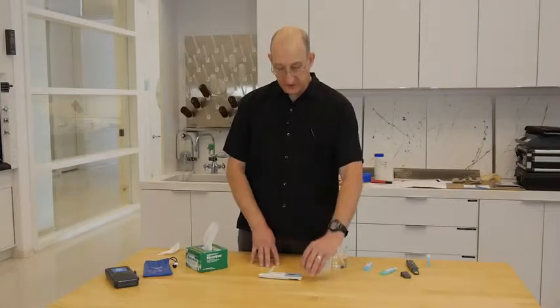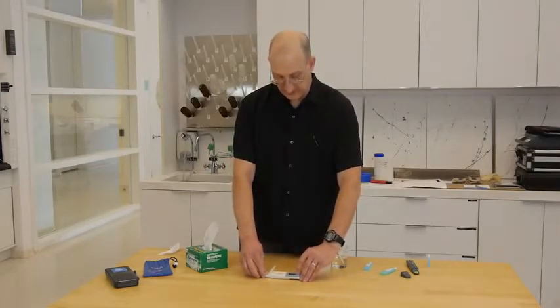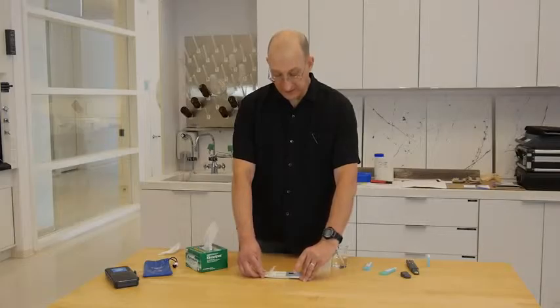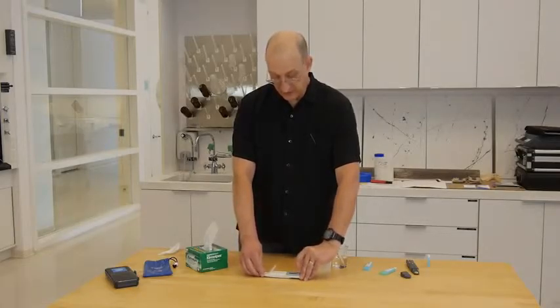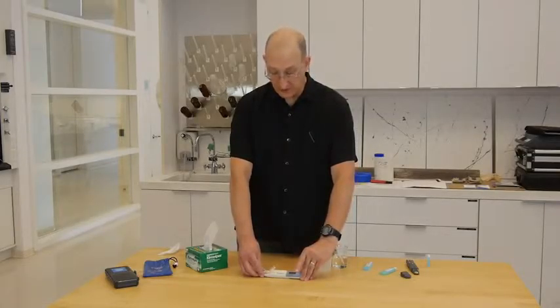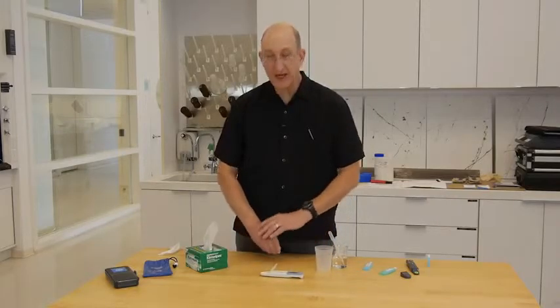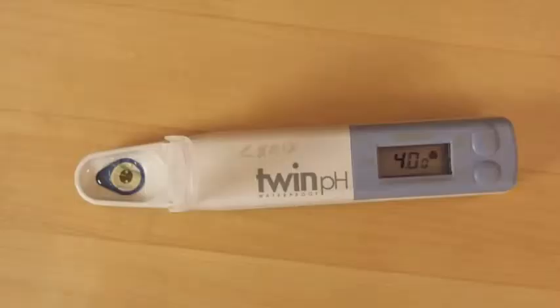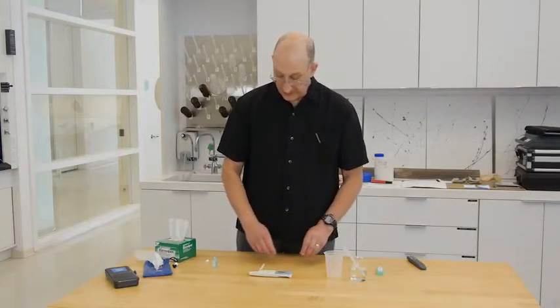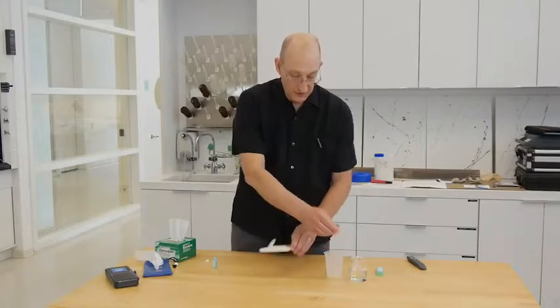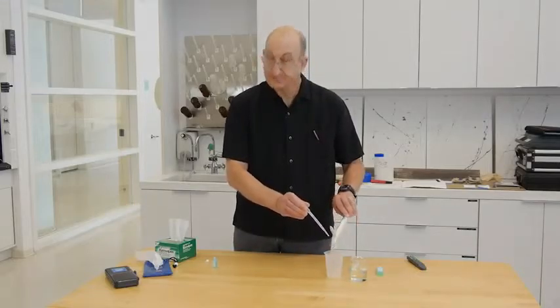We have our happy face, so we push the calibrate button. Initially, it wants to calibrate to pH 7. We don't want that. We push again, and we're now calibrating to pH 4. If we were calibrating to 10, we would push one more time, and we would get the calibration for 10. And we wait again for the happy face. We now have our happy face, and again, we just rinse with deionized water, and we're all calibrated. That's it.